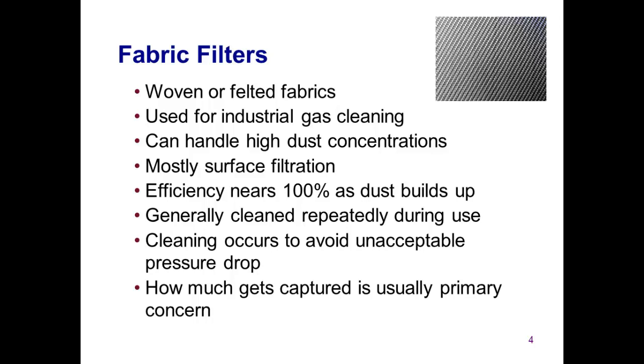pulse of air. Cleaning is performed to avoid an unacceptable pressure drop, and the cleaning is usually triggered at a set time interval or in response to an elevated pressure drop across the filters. The fraction of the incoming particles that gets captured is usually the primary concern in the performance of fabric filters, along with pressure drop.